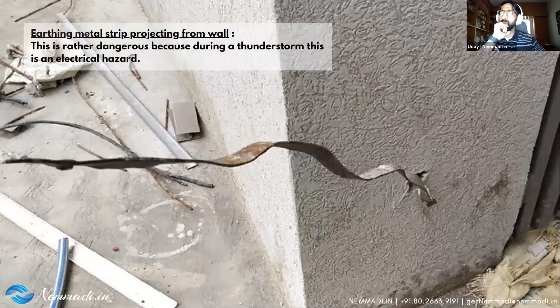This is an earthing strip which people think is connected properly, but if you look at it, it's a very shabby job. In this basement, some corners where these strips are supposed to be taken to a proper earthing pit, that has not been done. Only if somebody goes into the corner with technical knowledge will they be able to find out; otherwise, someone will think it's just a strip of metal and cut it off. This is a serious lapse because the earthing line gets cut off if you don't properly embed it in the concrete.